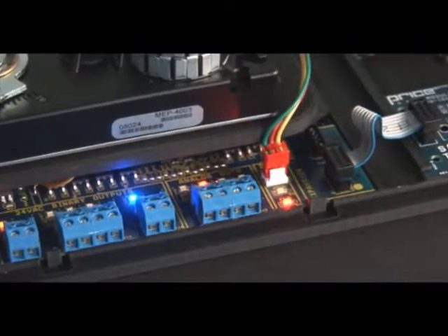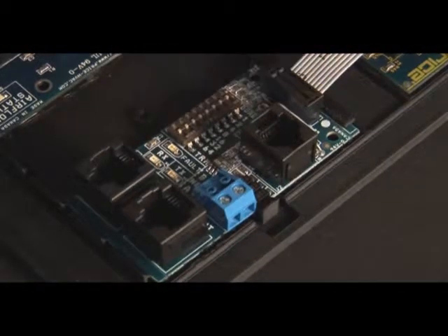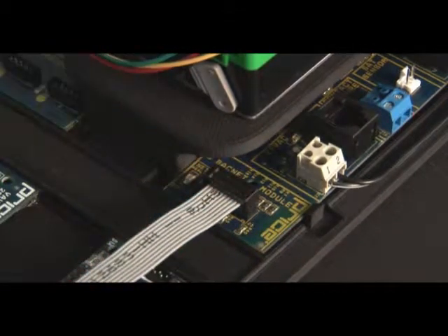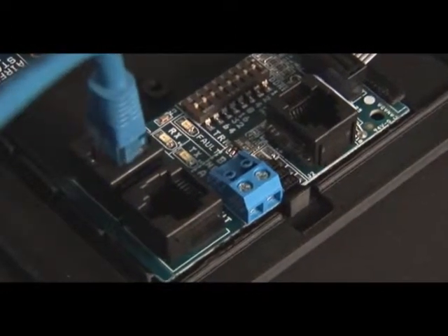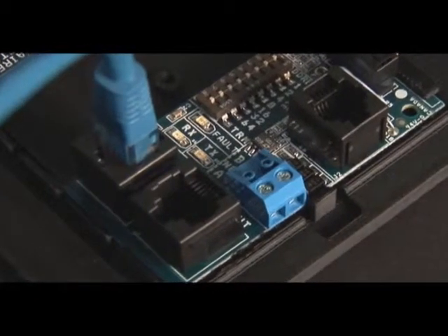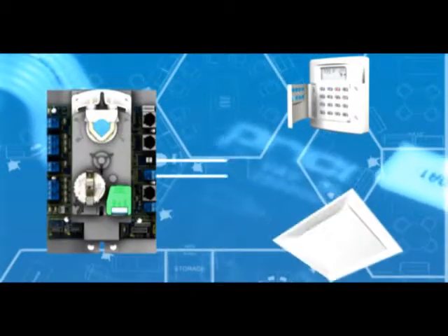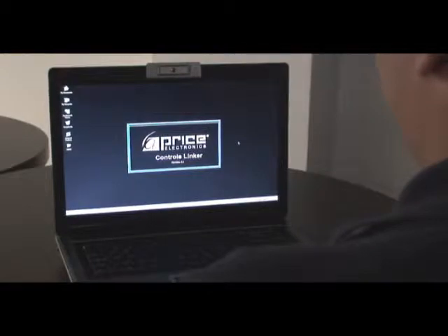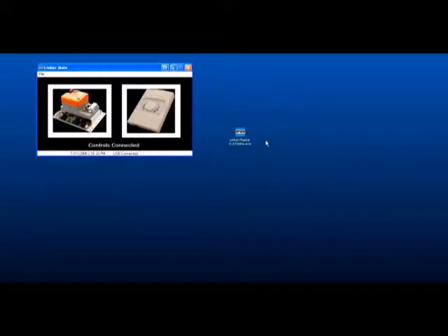The PIC is available with both BACnet and VAV expansion modules. If required, optional expansion modules connect by plugging the included ribbon cable into the PIC. The BACnet expansion module adds BACnet server capabilities to the PIC, allowing full integration into a building management system. This opens up the possibility of full integration with other Price BACnet-capable devices, such as the Price Digital Rooftop Controller and the Prodigy Self-Modulating Diffuser. This upgrade allows a contractor, engineer, or building manager to remotely access the unit via password-protected software over the Internet, which facilitates service and maintenance and eliminates site visits.